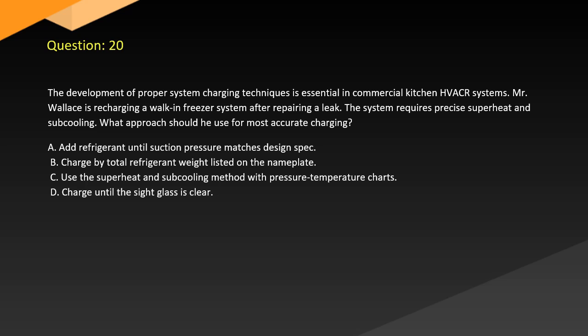Question 20. The development of proper system charging techniques is essential in commercial kitchen HVACR systems. Mr. Wallace is recharging a walk-in freezer system after repairing a leak. The system requires precise superheat and subcooling. What approach should he use for most accurate charging? A. Add refrigerant until suction pressure matches design spec. B. Charge by total refrigerant weight listed on the nameplate. C. Use the superheat and subcooling method with pressure temperature charts. D. Charge until the sight glass is clear.